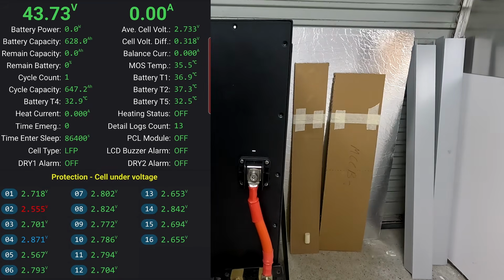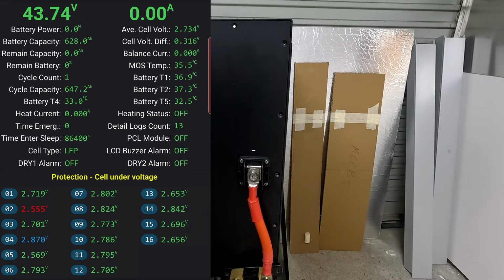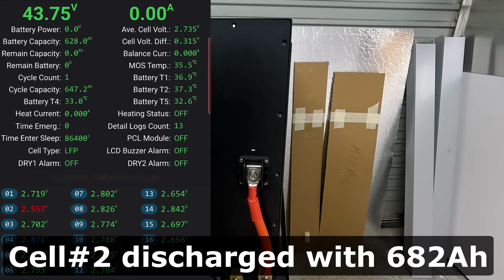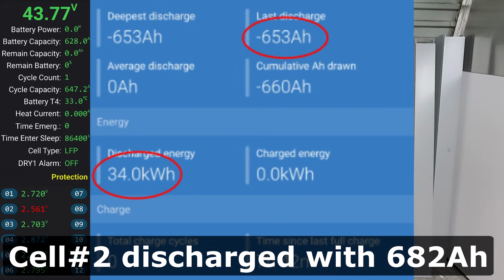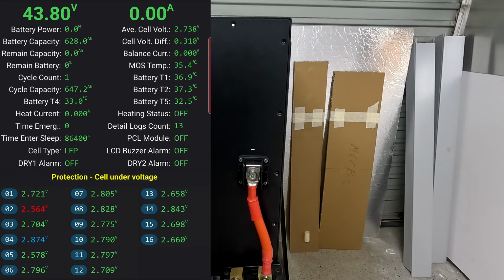We disconnected at 43.7 volts, with a deviation of 316 millivolts. Cell number 2 was our lowest. I'll put the capacity of cell number 2 on the screen; this time we discharged it to about 682 ampere hours. But this is normal: a single cell capacity test always gives you a bit more capacity than when that same cell is put into a full battery pack.